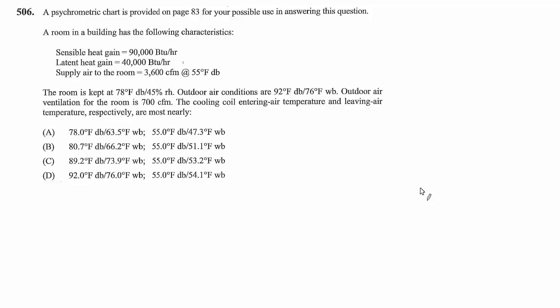A psychrometric chart is provided on page 83 for use in answering this question. A room in a building has the following characteristics: sensible heat gain 90,000 BTU per hour, latent heat gain 40,000 BTU per hour, supply air to the room 3,600 CFM at 55 degrees dry bulb. The room is kept at 78 degrees dry bulb, 45% relative humidity. Outdoor air conditions are 92 degrees dry bulb, 76 wet bulb. Outdoor air ventilation for the room is 700 CFM. The question asks for the cooling coil entering air temperature and leaving air temperature, given in terms of both dry bulb and wet bulb.